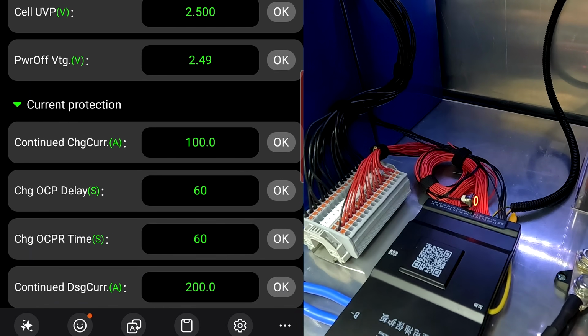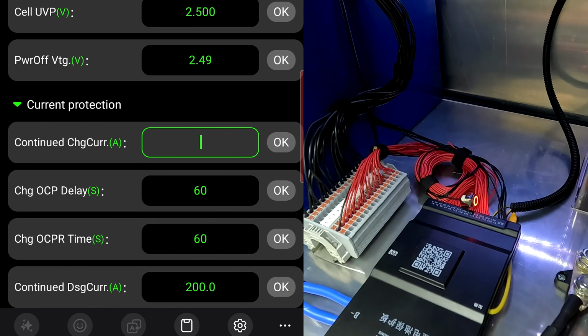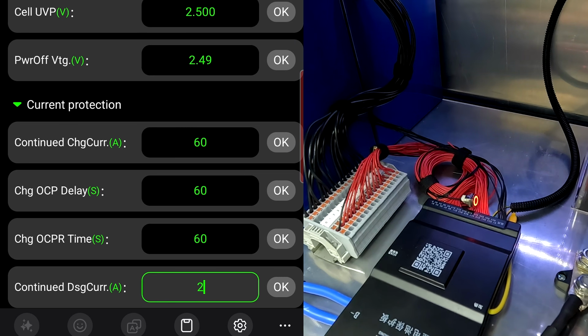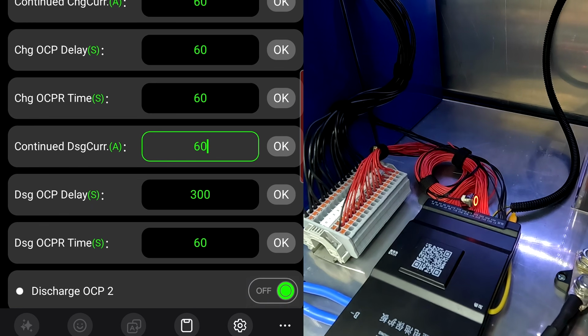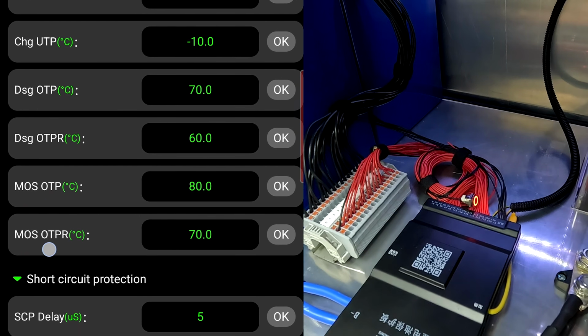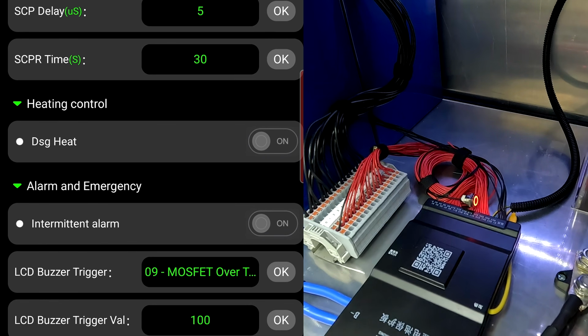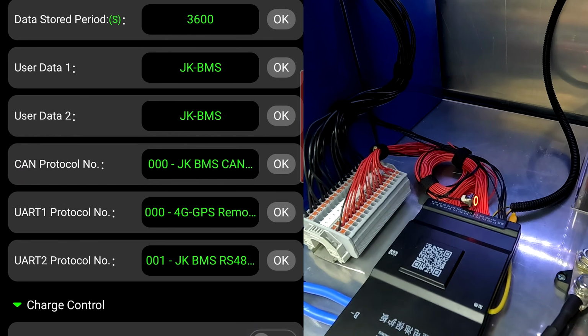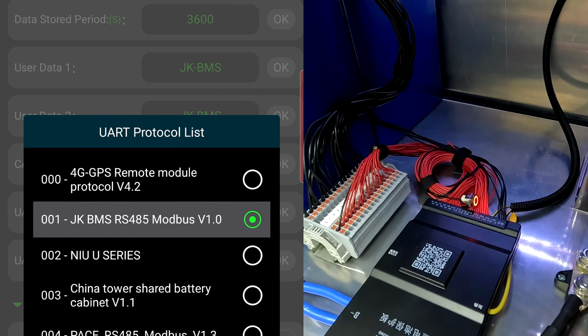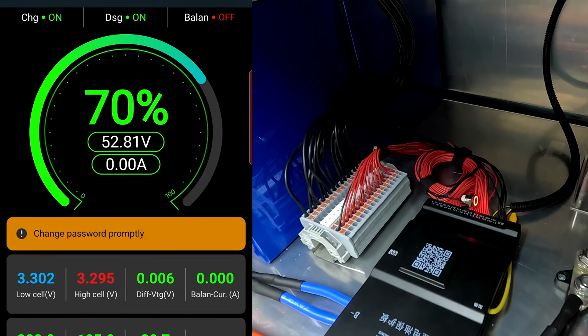Charge current 100 amps - okay, we'll set this one maybe to 60 amps only, and this one here to 60 amps as well, because I've got so many batteries in parallel, we don't need 100 amps per BMS or per battery. I think everything else is fine, so just ensuring the UART2 protocol sits on JK-BMS, Modbus version 1. That's pretty much it.